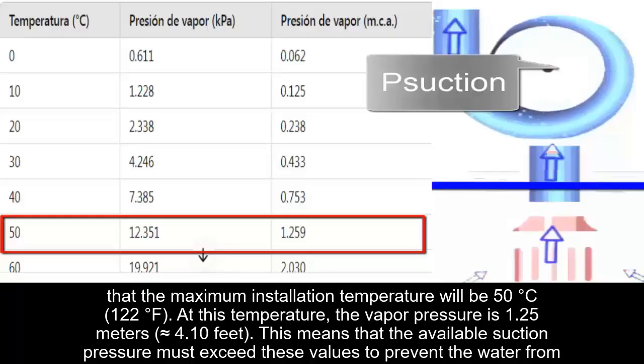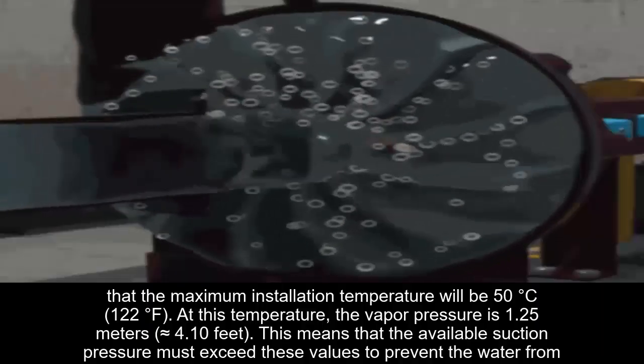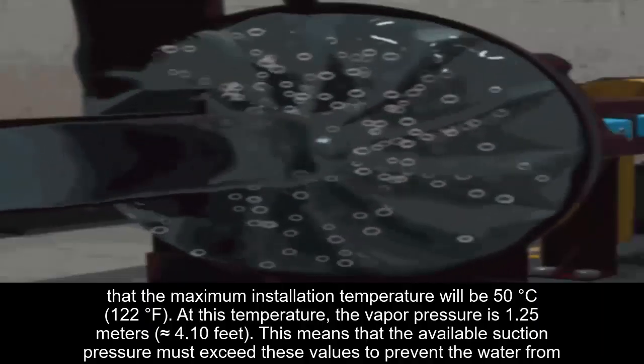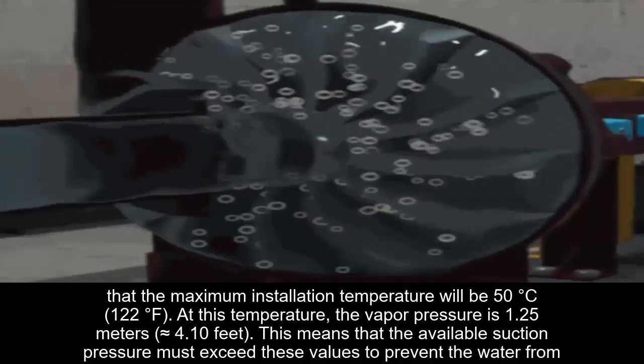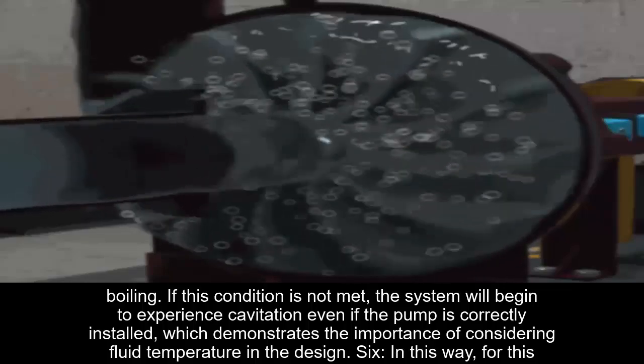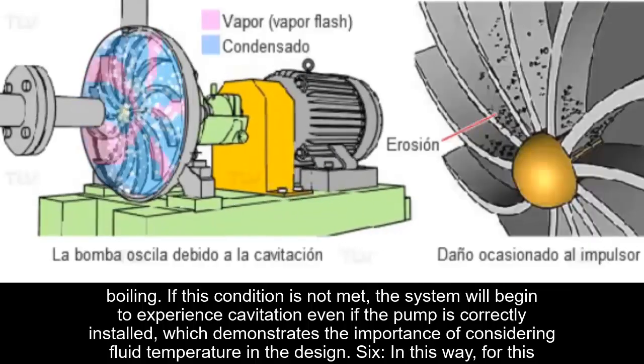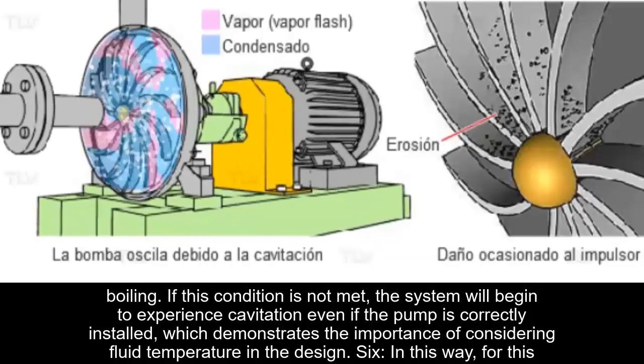5. For this case, we will consider that the maximum installation temperature will be 50 degrees Celsius, 122 degrees Fahrenheit. At this temperature, the vapor pressure is 1.25 meters, approximately 4.10 feet. This means that the available suction pressure must exceed these values to prevent the water from boiling.